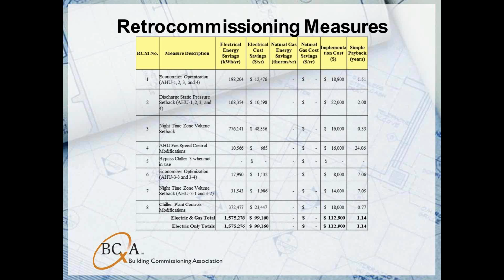Once we fix the issues with the plant, we can then implement RCM 1, which is economizer optimization, and that's basically just a set point change. We can raise the economizer lockout set point on the air handlers to be between 65 and 68 degrees and stop false loading our chiller plant.